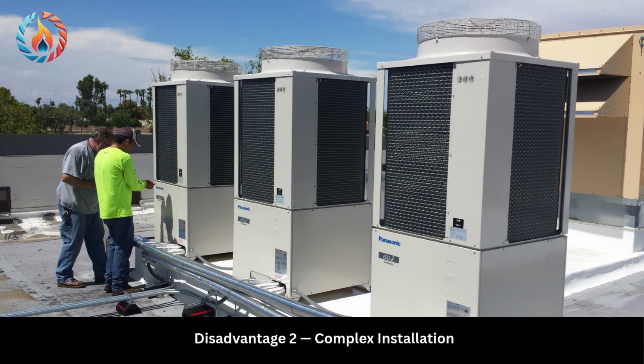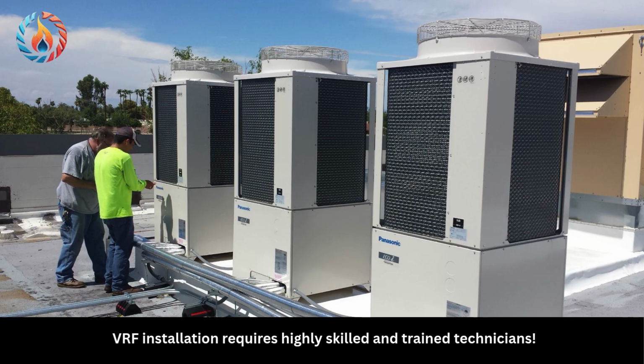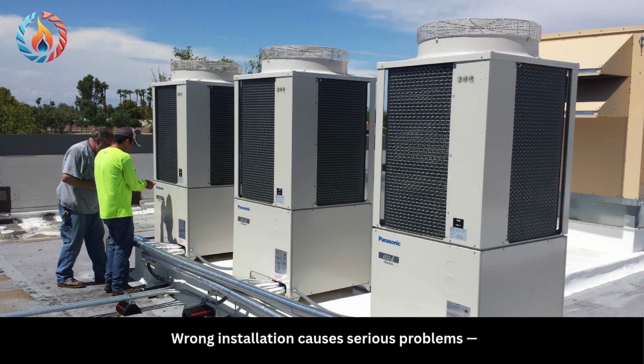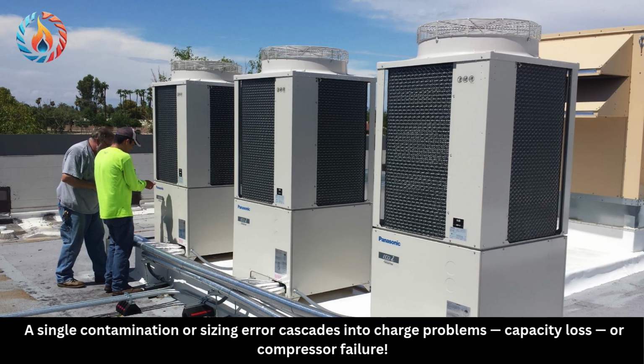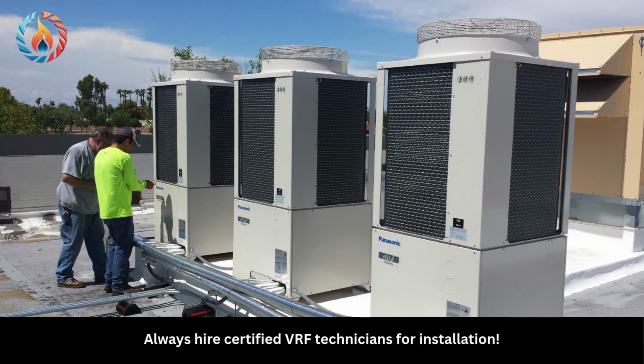Disadvantage 2. Complex installation. VRF installation requires highly skilled and trained technicians. Wrong installation causes serious problems. A single contamination or sizing error cascades into charge problems, capacity loss, or compressor failure. Always hire certified VRF technicians for installation.